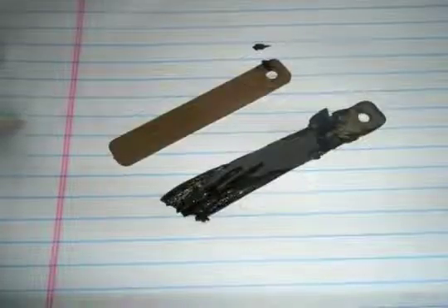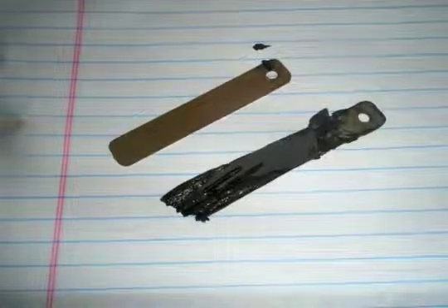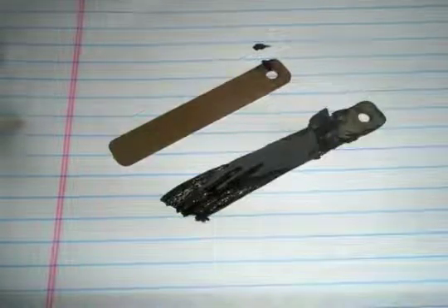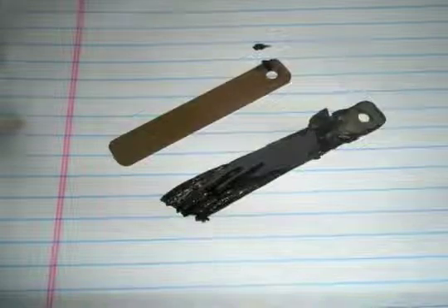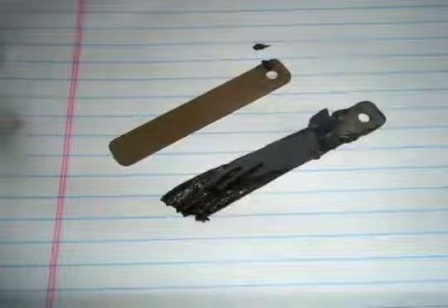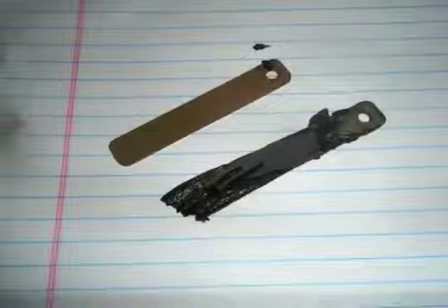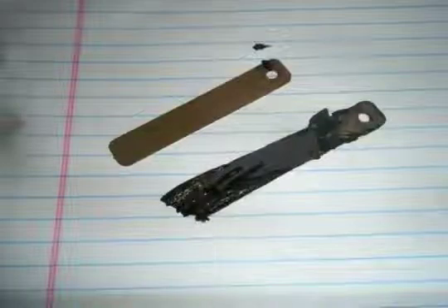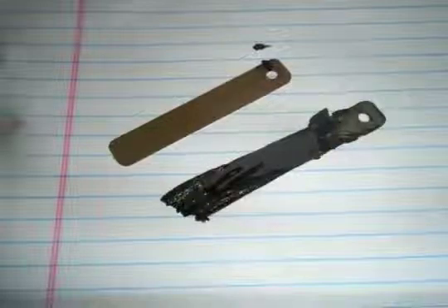Okay, so what's the impact of biological activity? These are corrosion coupons. Have you ever seen coupons? They're pre-weighed metal strips, either copper, and this one happens to be copper up here, and this happens to be steel here. This was actually pulled out of a cooling tower system in the south. The black streaks you see right here are not general corrosion of a coupon. This is all biological growth growing on the coupon itself, which simulates what could be growing on your pipe surfaces, your tube sheets, or everything else. And underneath this stuff is what's causing the corrosion, and that's called biologically influenced corrosion.